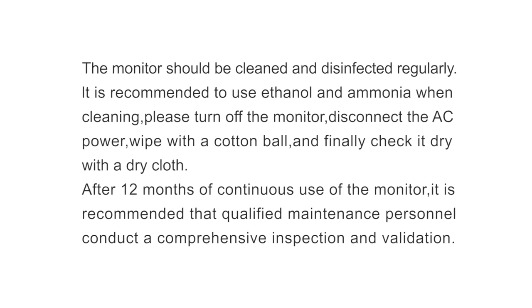The monitor should be cleaned and disinfected regularly. It is recommended to use ethanol and ammonia. When cleaning, please turn off the monitor, disconnect it from the AC power, wipe with a cotton ball, and finally dry it with a dry cloth. After 12 months of continuous use of the monitor, it is recommended that qualified maintenance personnel conduct a comprehensive inspection and validation.